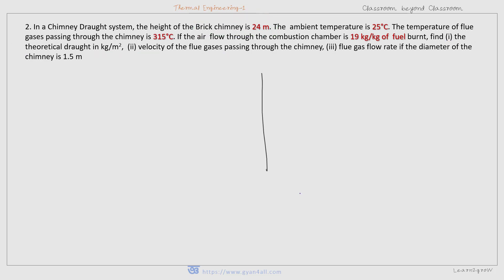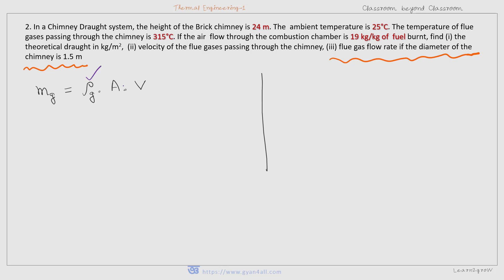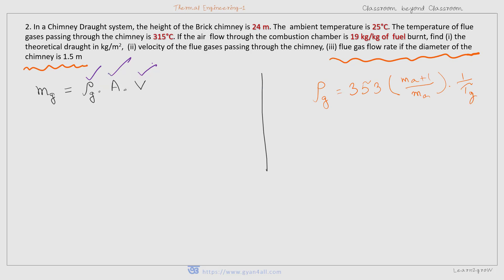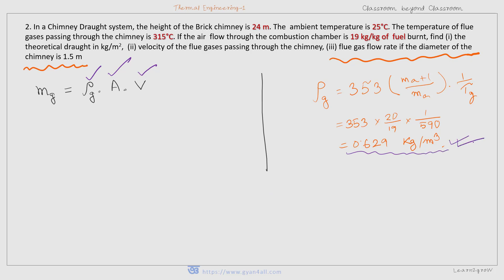For part three, we have to find the flue gas flow rate if the diameter of the chimney is 1.5 meters. The formula for mass flow rate is Mg equal to rho_g into A into V, where rho_g is the density of the flue gas inside the chimney, A is the cross-sectional area, and V is velocity. First, we find the density of the hot gas. Using the formula with Ma and Tg — Ma plus 1 is 20 (that is 19 plus 1) — the density is 0.629 kg per meter cube.